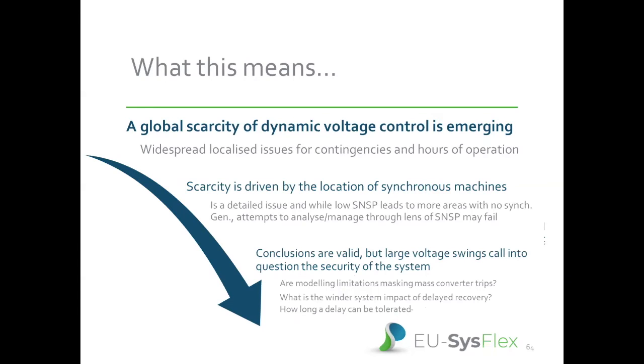And the first of those, as I mentioned earlier, we have a clear global scarcity of dynamic voltage control. We will have widespread issues at very high SNSP, and even at lower SNSP, we will have localized issues emerging, where certain contingencies always present a problem, and certain conditions will always have a problem for all contingencies. So there's a real problem coming down the line in terms of this dynamic voltage control scarcity, and we've got to find some answers. The scarcity is very driven by the location of synchronous machines, is what we found, and this was true in both LCL that I've spoken through there and the less ambitious steady evolution scenario. And what basically emerges is that you have regions of the system where you have very few synchronous machines or even no synchronous machines. And as they are currently our primary source of dynamic voltage control, those regions effectively get abandoned. And as you increase SNSP, the likelihood of those regions increases.